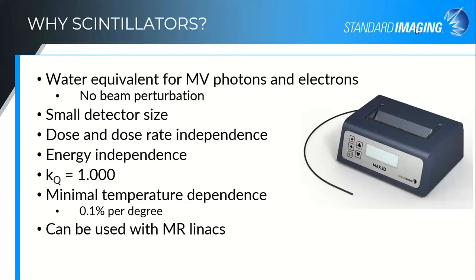The reason that scintillators are such an interesting detector right now is multifaceted. The crux of it is the water equivalence for megavoltage photons and electrons. As we're trying to meet the challenge of small field dosimetry — trying to get down to fields that really are comparable in size to the detectors we're using — the composition of the detector comes into play much more than it does with larger fields. Not perturbing the beam right there at the point of measurement becomes a huge advantage. The ability to make these detectors small so we can get down into those really small fields is also an advantage of scintillators.